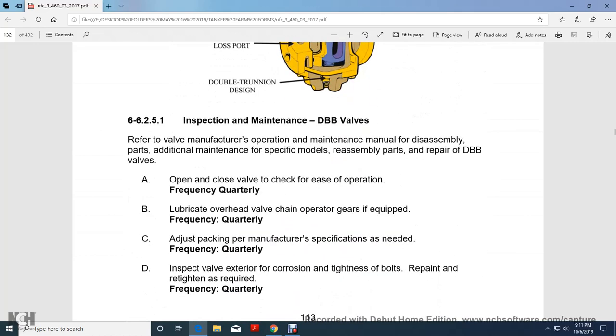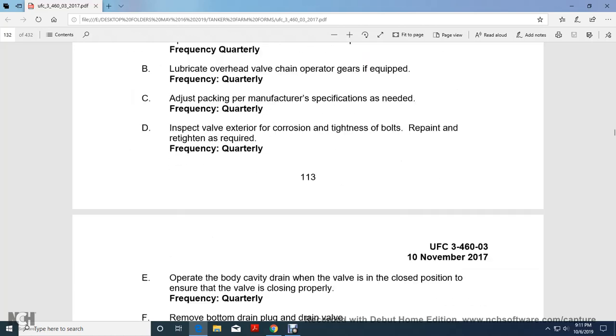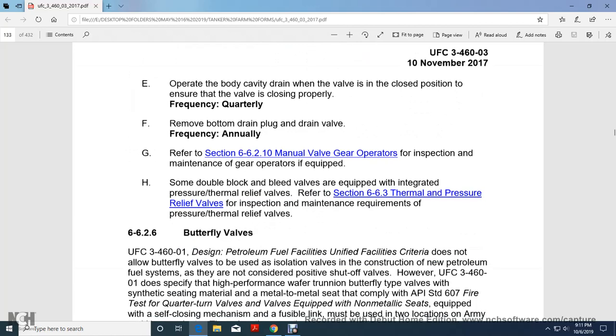Inspection and maintenance of the double block and bleed valve: refer to the operation and maintenance manual for disassembly of the parts, additional maintenance specific to the model, and reassembly of the parts for repair of the double block and bleed valves. Open and close the valve and check for ease of operation quarterly. Lubricate the overhead chain operator, if equipped, quarterly. Adjust packing per manufacturer, inspect quarterly. Inspect valve interior and exterior for corrosion and tightness of bolts, repaint and retighten as required, quarterly. Operate the body cavity drain of the valve in the closed position to ensure the valve is closing properly, quarterly. Remove the bottom drain plug with the drain valve annually.